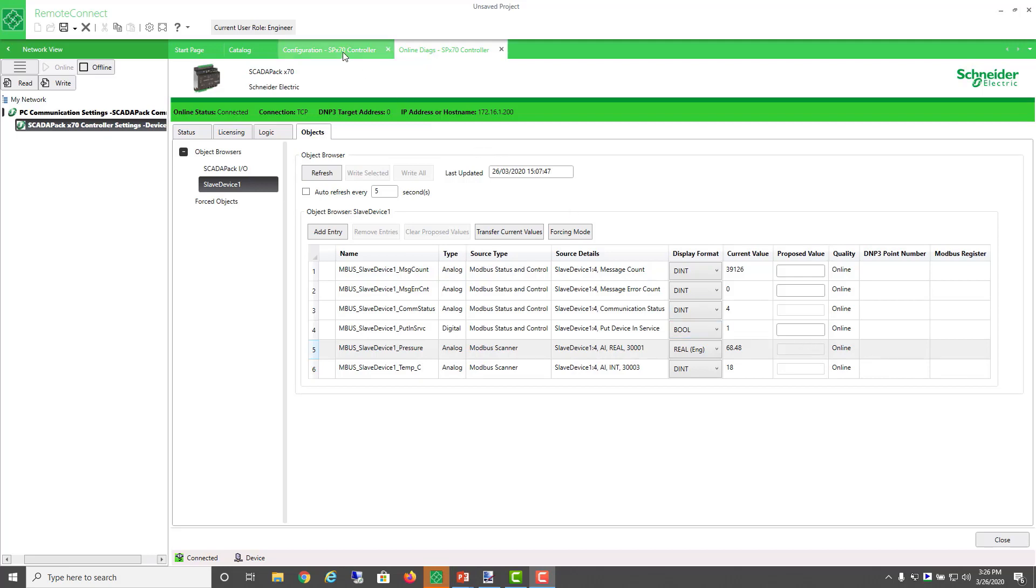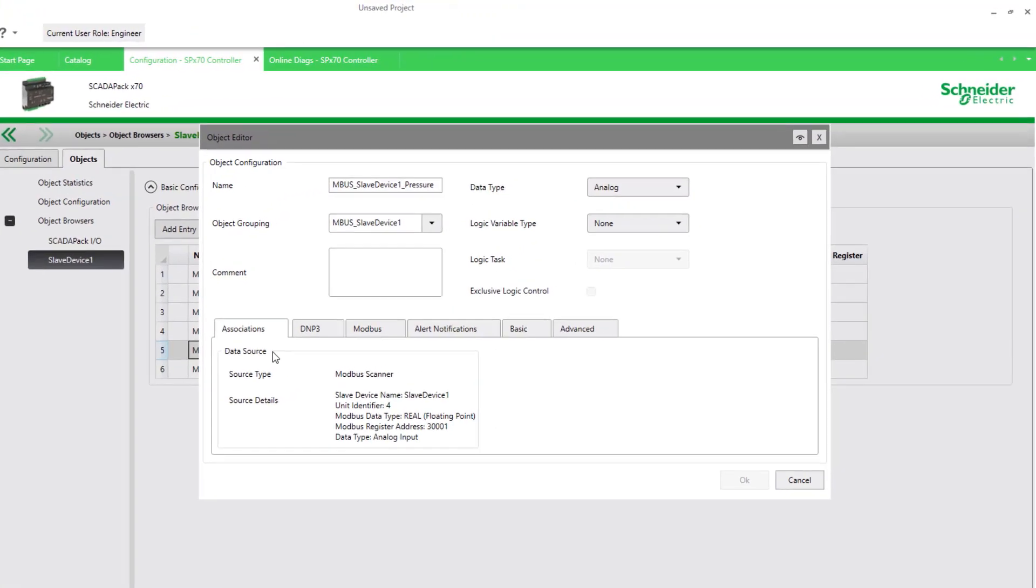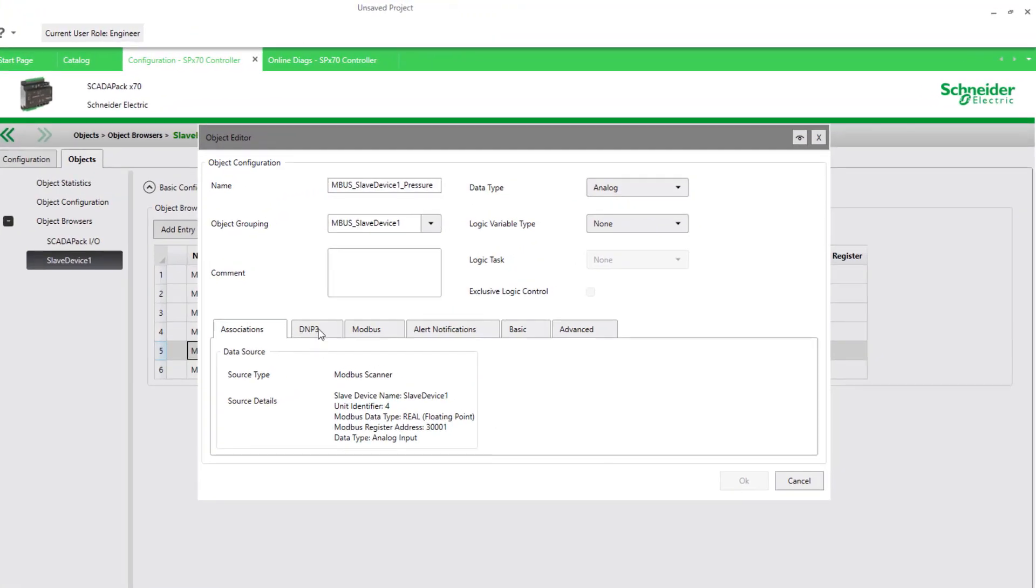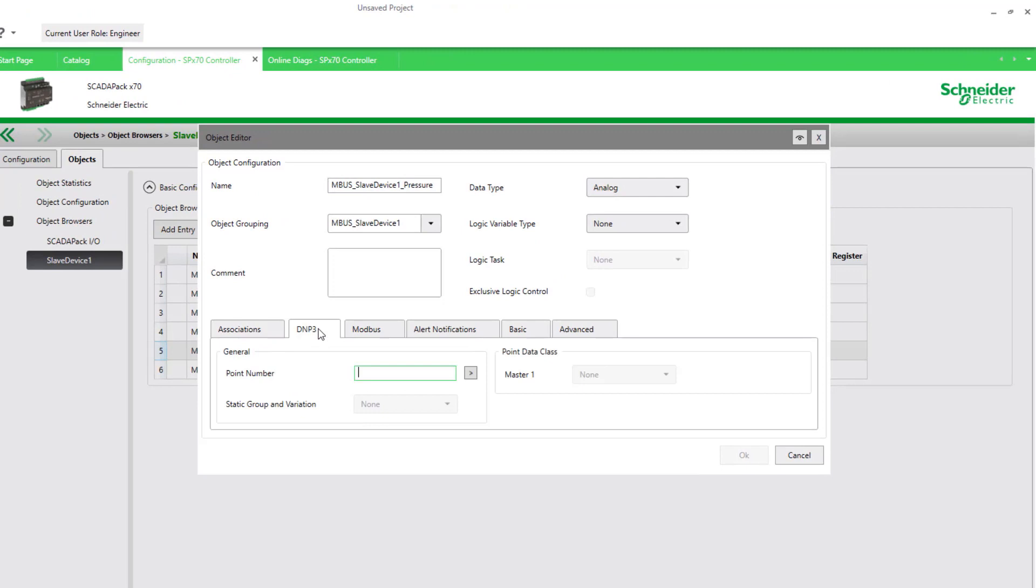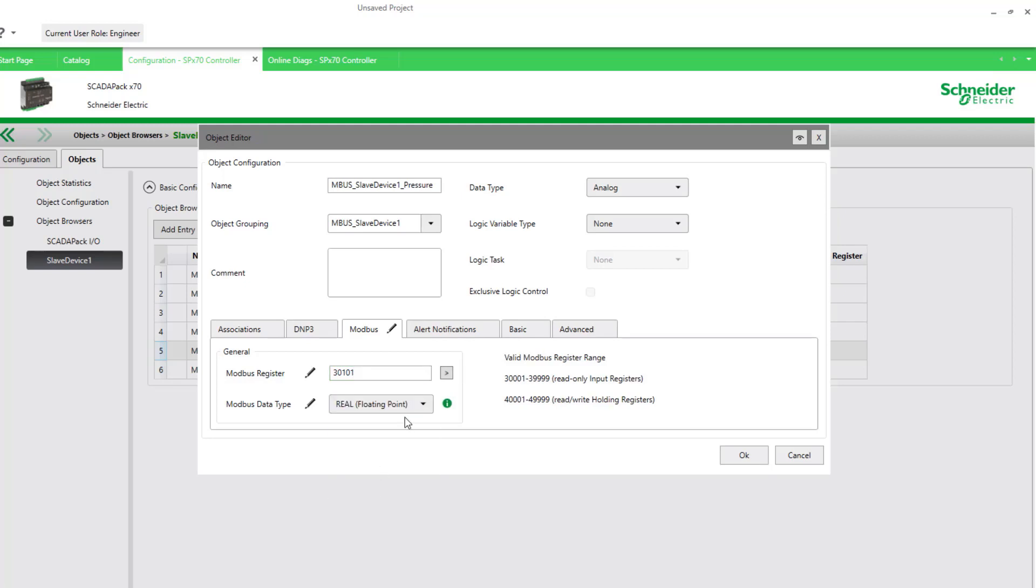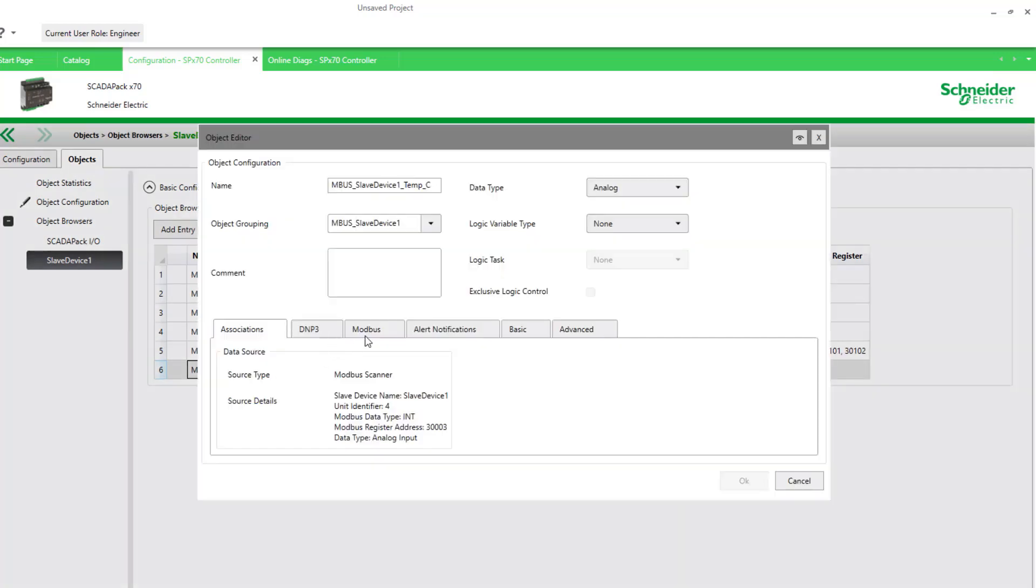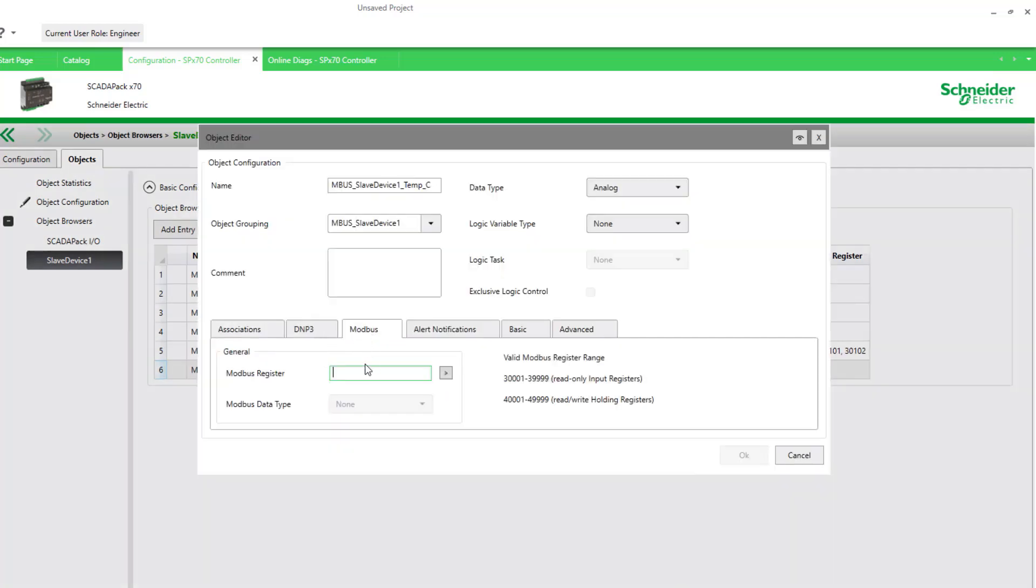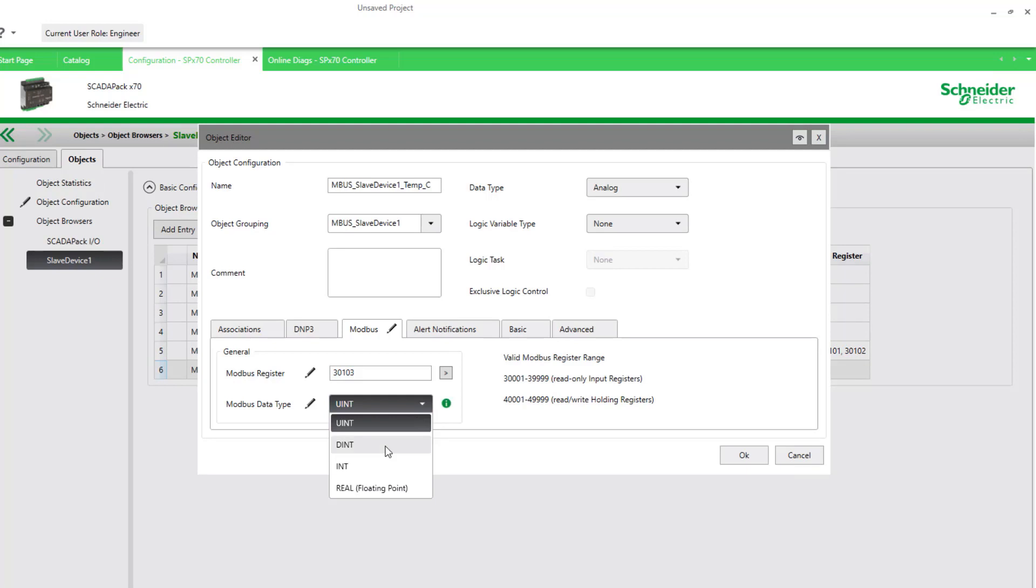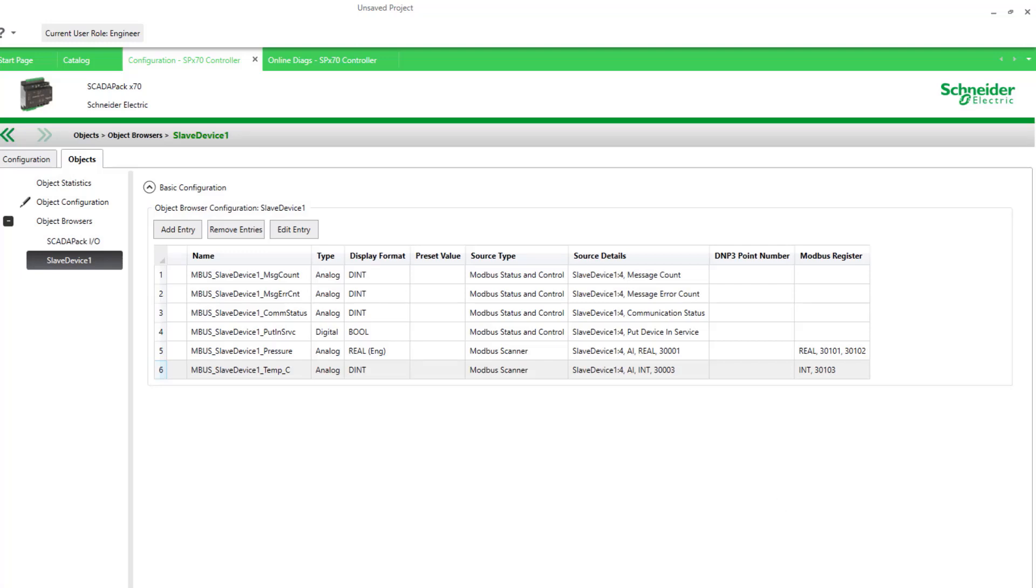I switch to the configuration view of my object browser and double-click this object first. This is where I assign a DNP3 address, and here is where I assign the Modbus. I'm going to use 30101, and I'll select the real format. For my temperature, I'll assign the address 30103, and this will be a signed integer. Applying that.